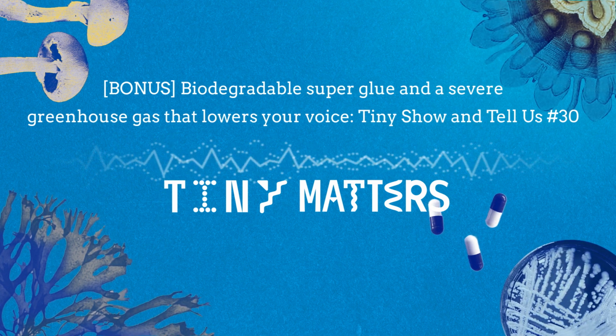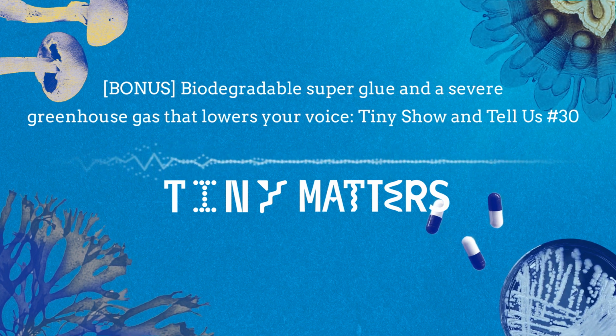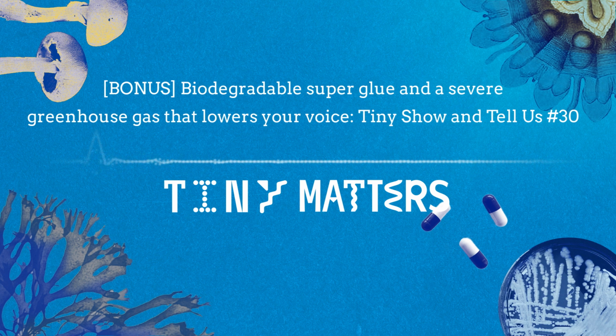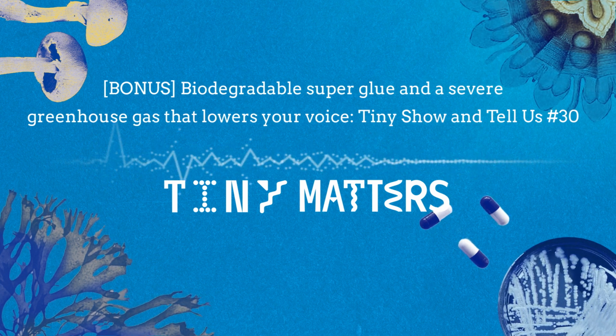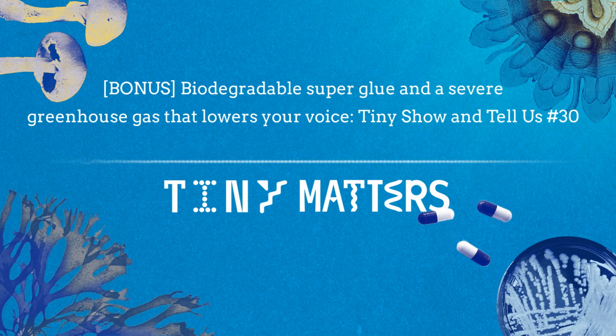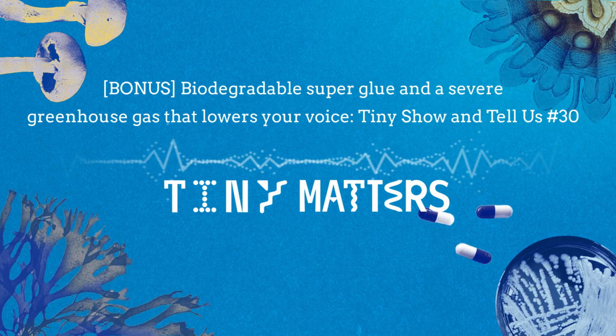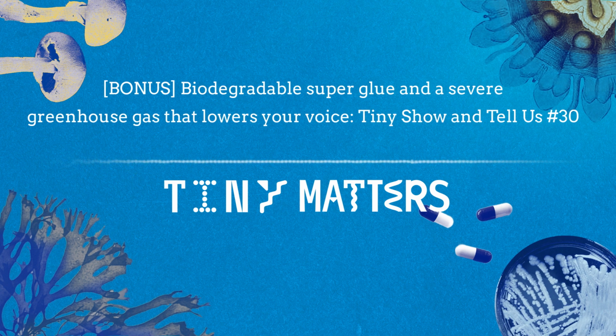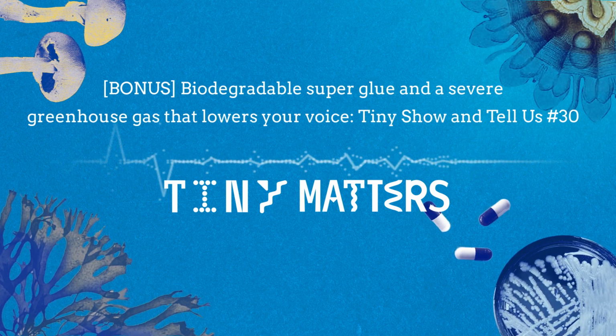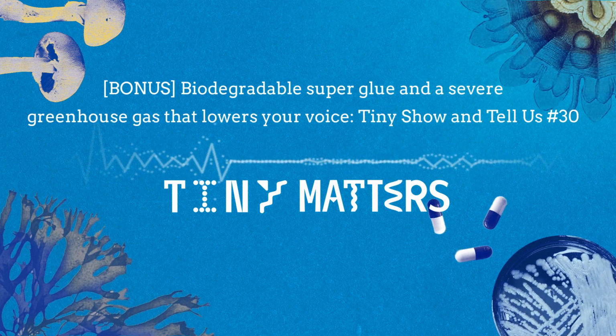So SF6 gas circuit breakers use sulfur hexafluoride as what's called an arc quenching insulating medium, which really just means that it's a material that stops the electrical arc that forms when a circuit is open. So it absorbs that energy and then blocks it from continuing to conduct electricity. And apparently it's much more effective at dissipating heat than other elements or compounds like air or nitrogen. And so there are a lot of things about it that sound kind of great, right?